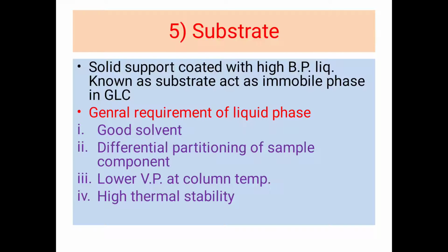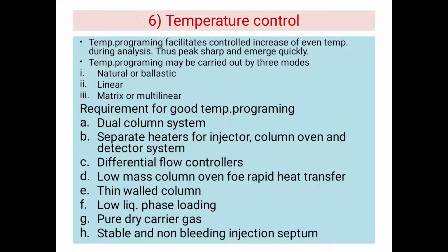Next we discuss the temperature control system, that is, the thermostat chambers used in the GC. Temperature programming facilitates controlled increase of even temperature during an analysis, and thus peaks become very sharp and emerge quickly. Thus, with temperature programming, components of a wide boiling range in a mixture may be resolved efficiently.